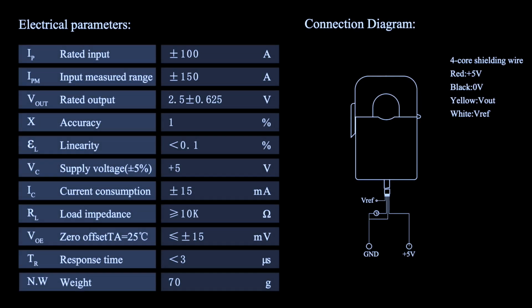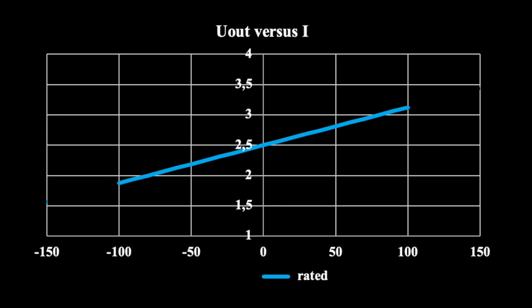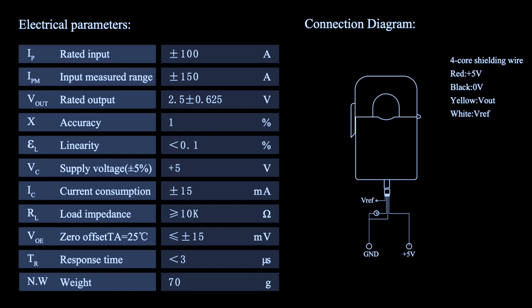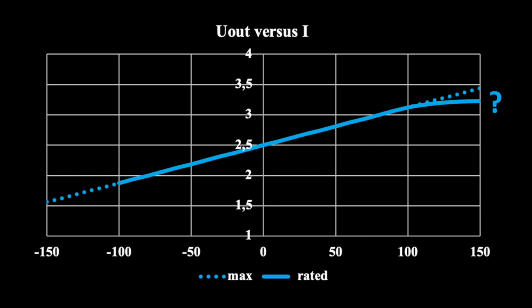The accuracy of a measuring device applies within its rated range, which is ±100 amps in our example. The nominal output voltage is in the range of 2.5 ± 0.625 volts. The sensor's characteristic is a straight, or at least an almost straight line, as we will see in a minute. The datasheet is also specifying an extended input measured range as ±150 amps. However, outside the rated range, the characteristic is deviating from a straight line. I'm exaggerating this in the diagram to show the saturation effect.